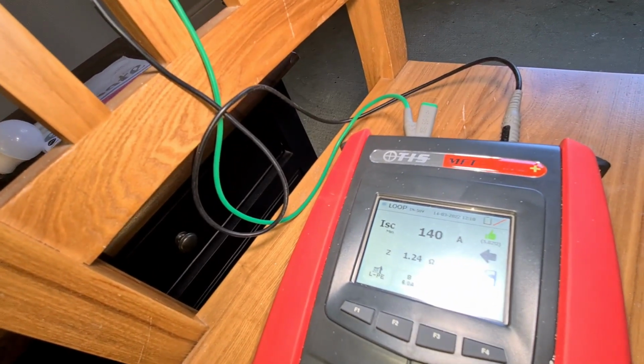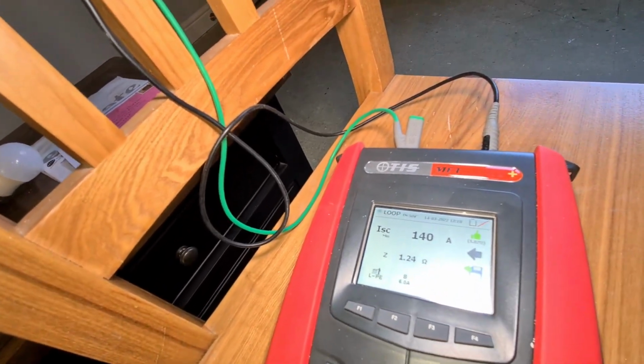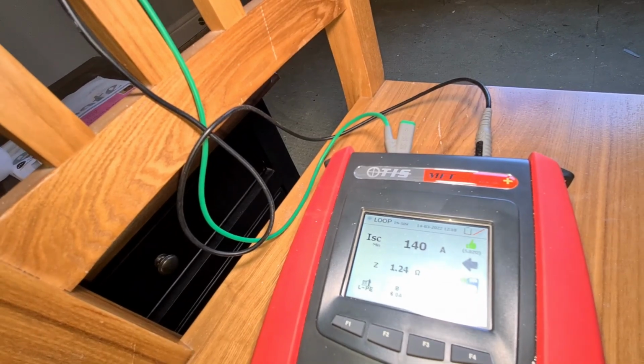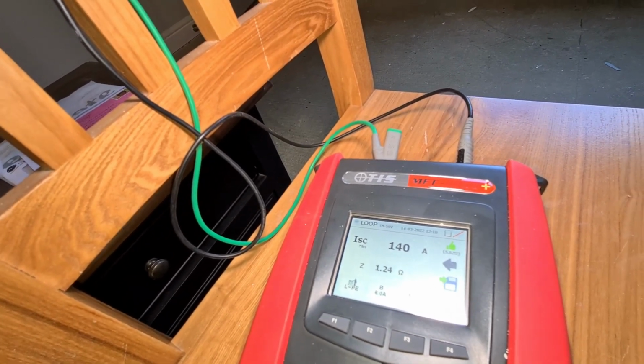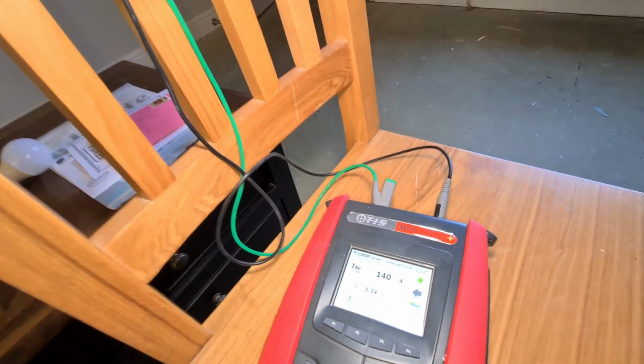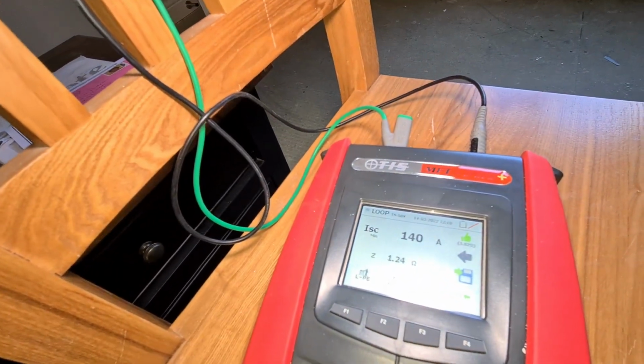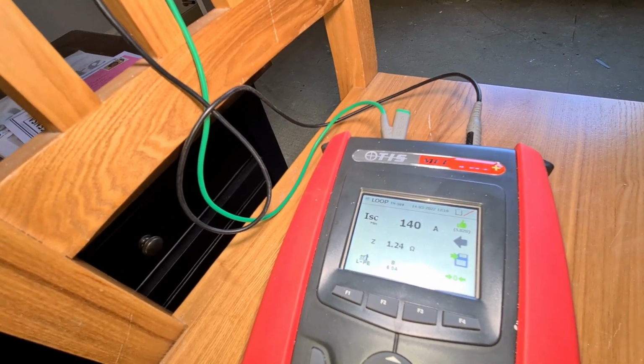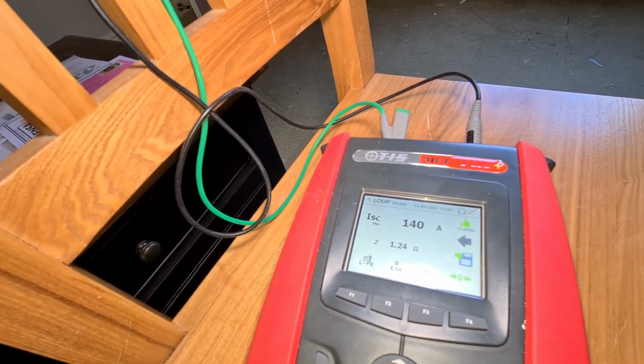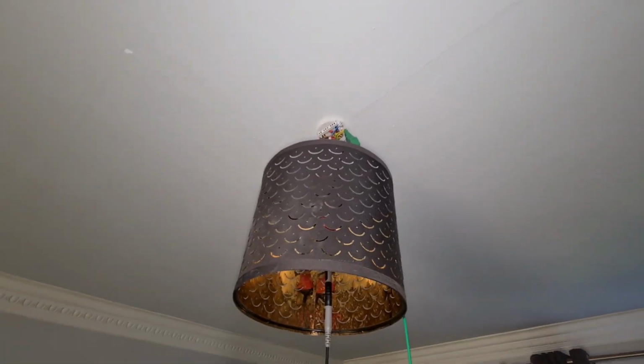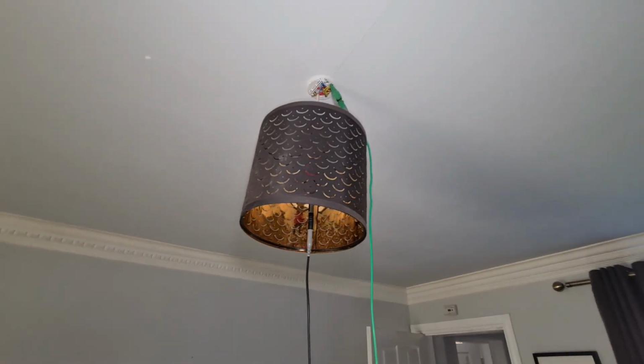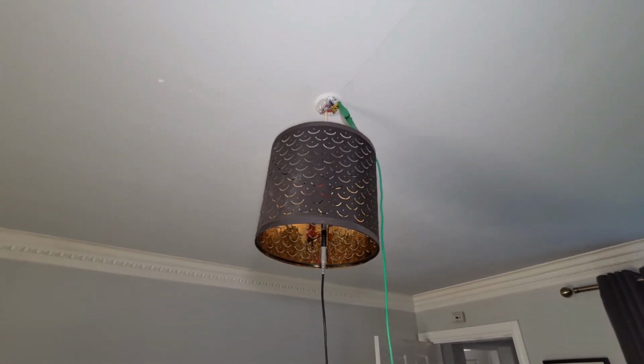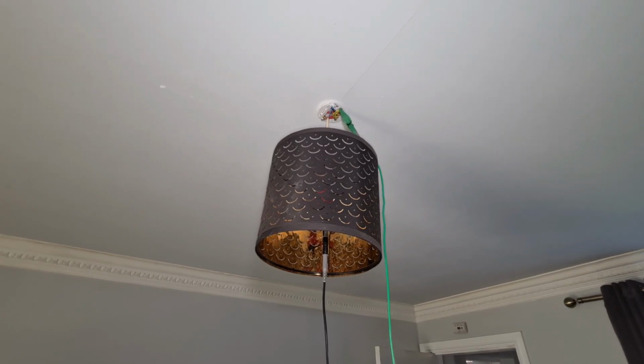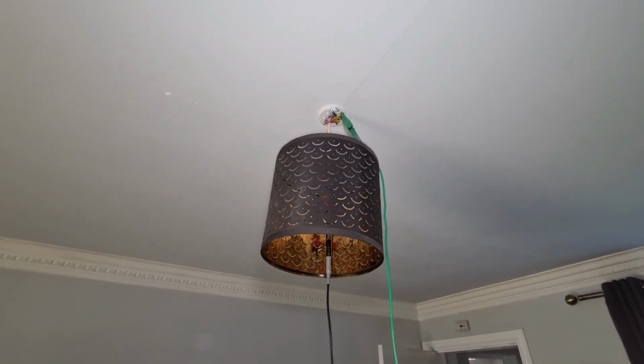And you can see I've got 1.24 ohms and 140 amps as my prospective fault current, if you like, at this point in the circuit. Now that is considerably higher than the dead test measurements I was getting, and there's a good reason for that, and we'll explain why in a little minute. But if we look up there now, I can go off and disconnect the MCB again, open it, remove all of these connections and put it back together, and then do my functional check to make sure that the lamp actually illuminates. So that's the earth fault loop impedance done on the lighting circuit.